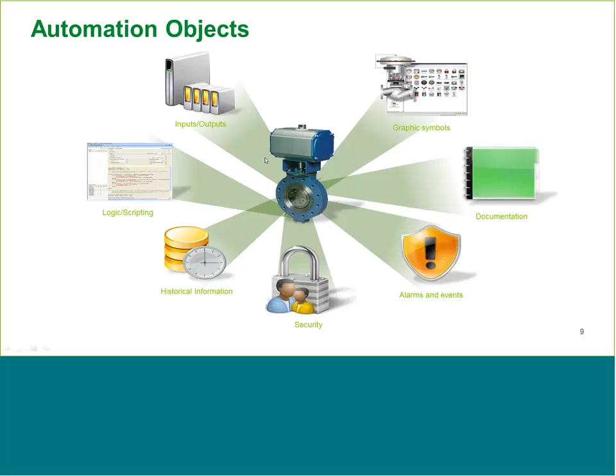System platform development begins with an object, and then you can create templates from these objects. So if we start with that valve object, and we've got maybe two different types of valves, an inlet valve and an outlet valve, I can create a derived template from my parent valve, and the inlet and outlet inherit everything from their parent valve object. Then I've got runtime instances of my inlet and outlet valves, which might also have unique attributes. So what this means is if I ever make a change to my parent valve template, or the inlet or outlet template, I can drive those changes down to the children instances. Corey's going to talk about how that helped decrease the engineering effort and time in designing, developing, commissioning, and validating the control system.